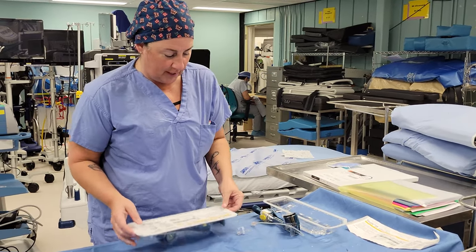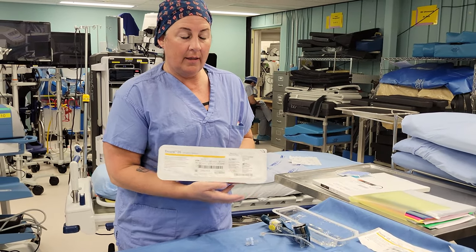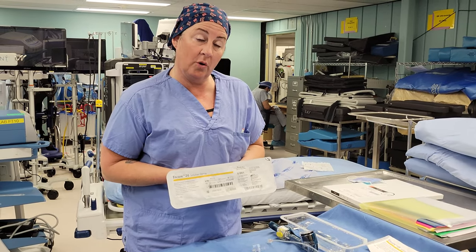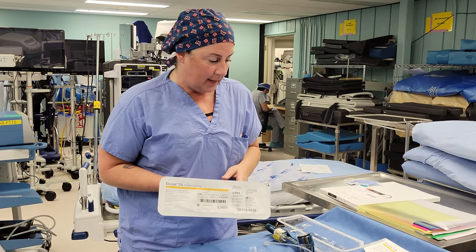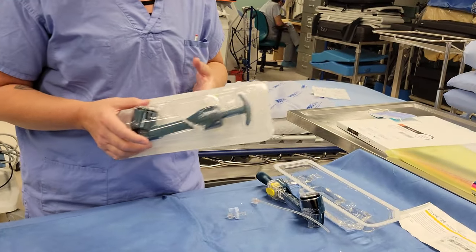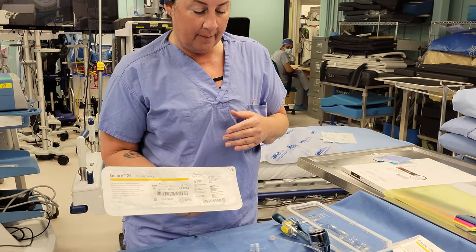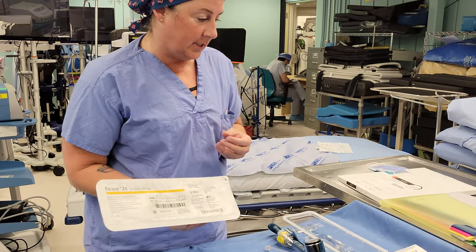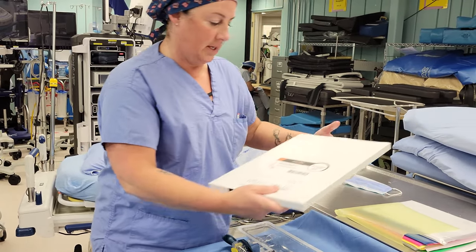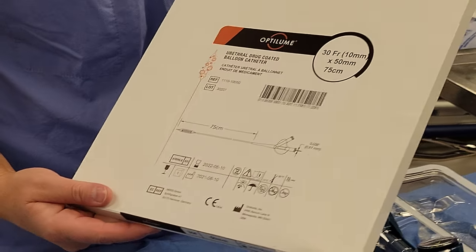We're gonna talk to you guys about the Encore inflation device. This lives on the bottom right-hand side of the EBAR Angio cart that lives outside room 8. You will use this item, and it's sterile for vascular. We would use it for any of our balloon catheters and or stents. And for urology, you'll be using it for the urethral balloon catheter for urethral dilatations.